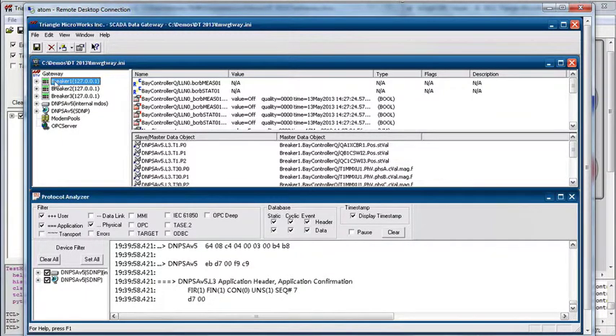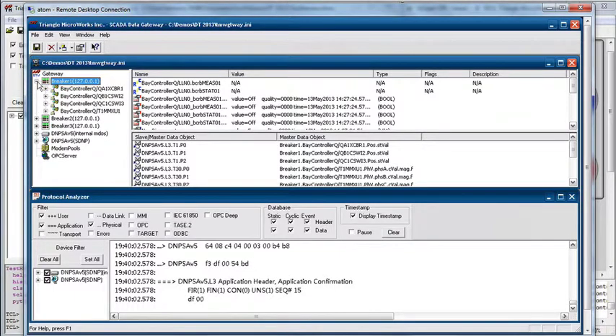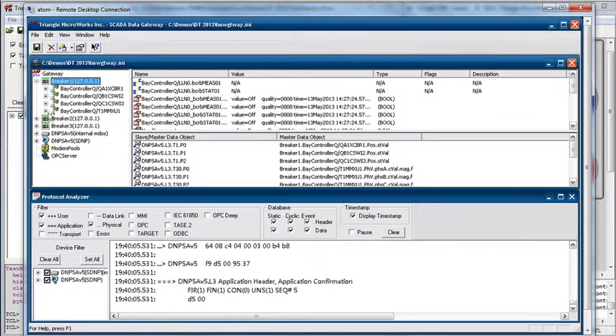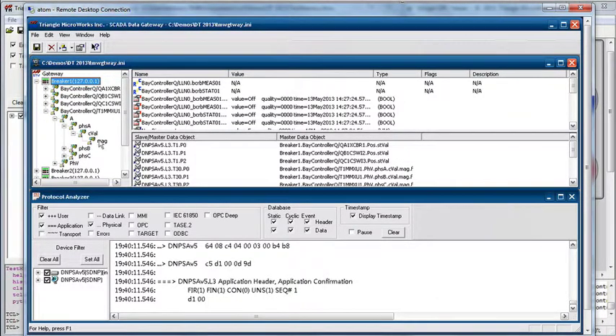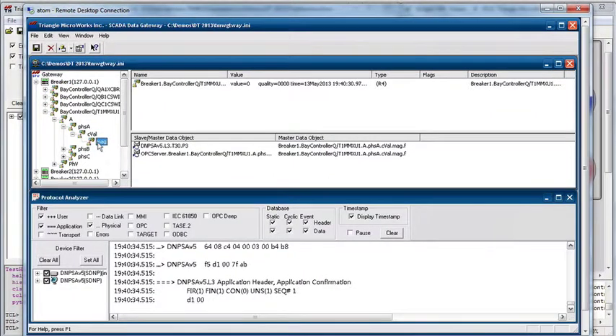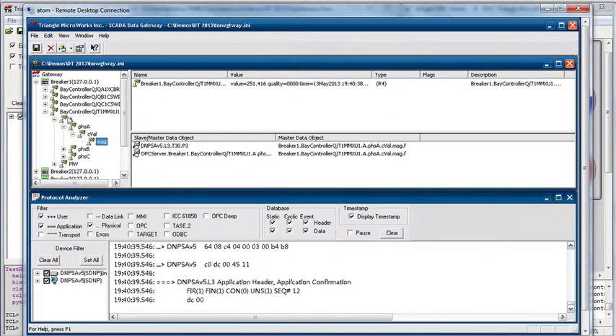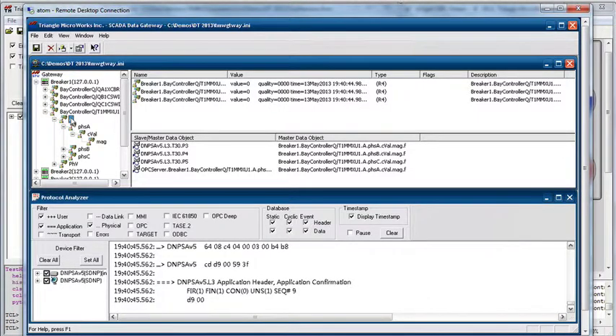If we look at one of the IEC 61850 client connections, we can expand it out and see the various report control blocks, and expand further down to individual points. One nice feature of the SCADA Data Gateway is that it will summarize the points below. For example, clicking on 'A' will show all the A values — phase A, phase B, and phase C currents.